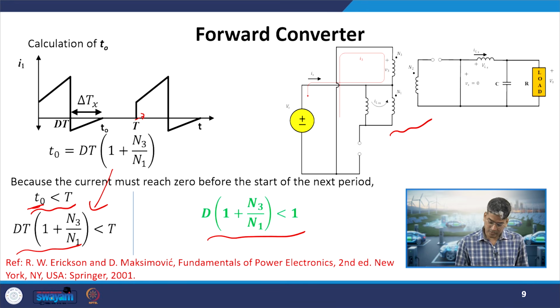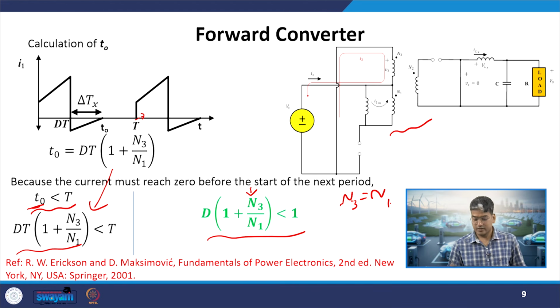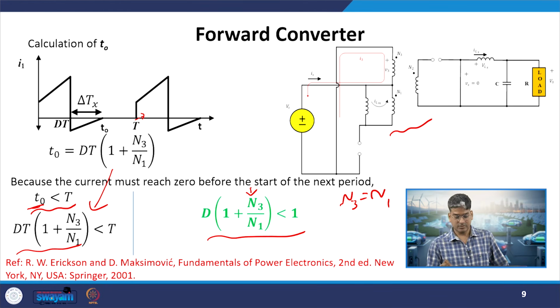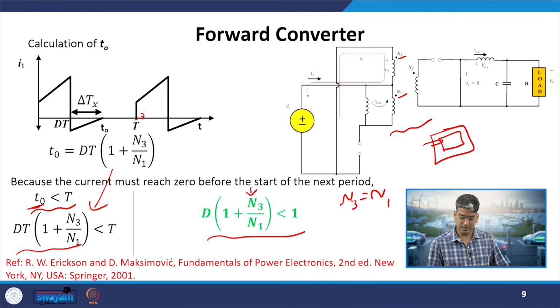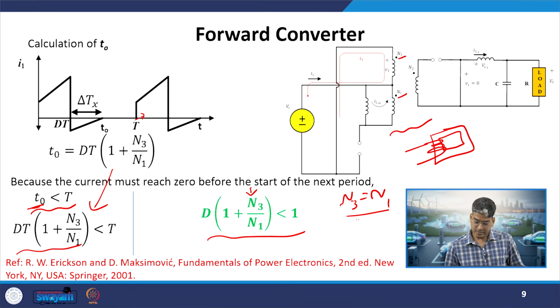Now for the time being, if I assume n3 equal to n1 -- why do we assume this? During construction, to reduce cost, generally n1 and n3 are wound together. What does that mean? On one leg of the transformer core, we simultaneously put two wires, which will be n1 and n3. Obviously the thickness will be different because they are subjected to different currents, but they generally have the same turns ratio because they are wound together.